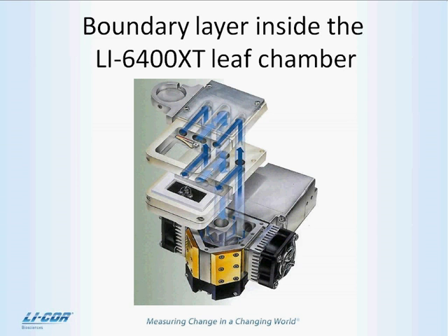The higher wind speeds inside the LI-6400 leaf chamber are employed to ensure that boundary layer resistance is a small part of the total leaf resistance to the movement of water, so that stomatal conductance measurements are not subject to uncertainties in the boundary layer conductance estimates. Conductance is just the inverse of resistance, and we seem to use them interchangeably.